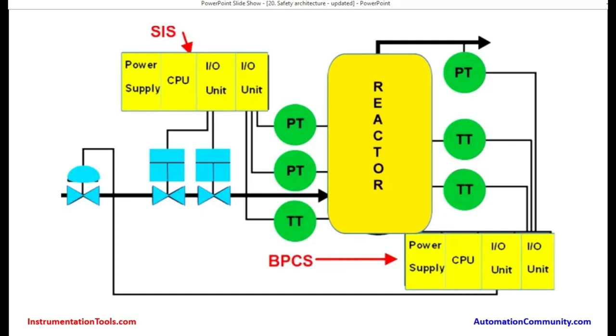It could be a redundant processor or triple modular redundant, where there will be three processors together performing similar functions. In case one fails, the second processor takes over; in case two fail, the third one takes over, and it is still able to take the action. However, it is not safe to run with a single processor in case of a triple modular redundant design. There are other safety requirements for the functionality of the logic solver. These transmitters will give a signal to the safety instrumented system, and after performing the logic, the output will go to the valves to shut the process.